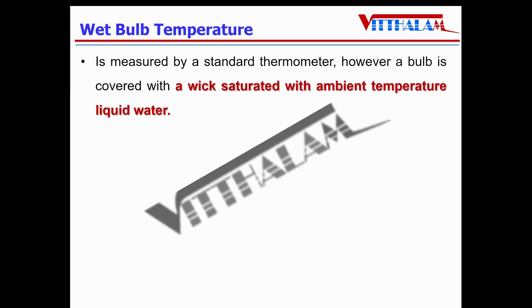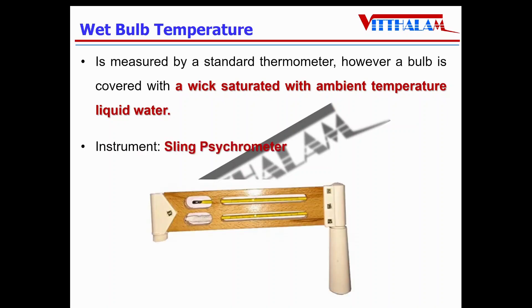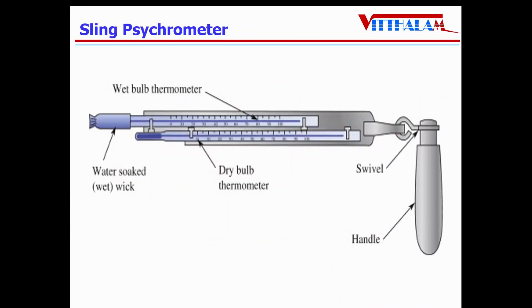Another one is the wet bulb temperature, which is measured by a standard thermometer. However, the bulb is covered with a wick saturated with ambient temperature liquid water. The instrument used to measure wet bulb temperature along with dry bulb temperature is known as a sling psychrometer. It is a very simple device containing two thermometers — one of which is dry and the second one is covered with a wetted wick.